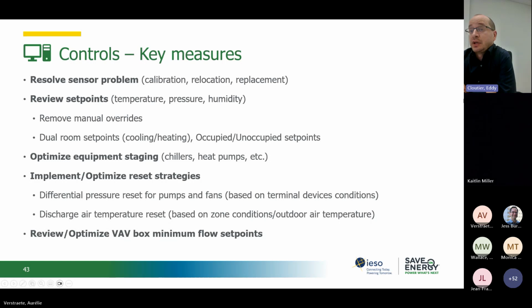So here's a summary of control measures. And as I was saying earlier, there are many more control measures that could be detected in the investigation process of the EBCX. But here are the most common: resolve sensor problems such as calibration, review set points, optimize equipment staging. This one is more for more complex chilled water plants or heating plants, where you have a lot of different types or capacities of equipment. So a good review of the programming of the different staging of equipment is always good. Next, implement and/or optimize reset strategies, such as we've seen earlier, and review and optimize VAV box minimum flow set points.